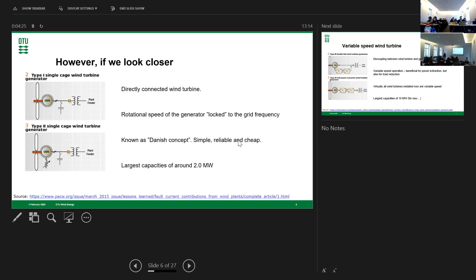The first two were directly connected wind turbines, type 1 and type 2, directly connected to the grid. The classification of wind turbines is based on their connection to the grid: if directly connected, the rotational speed of the generator is locked more or less to the grid frequency. This is known as the Danish concept, and they were very simple, reliable, and cheap wind turbines. They did a lot of work, and still today a large part of the wind turbines installed in Denmark are of this type. But their development stopped around somewhere around 2 megawatts as a capacity, if I'm not very wrong.